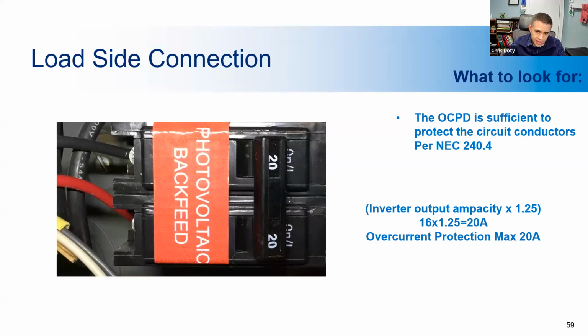Here you can see the standard calculation to determine the sizing of the circuit breakers and the fuses. Take 125% of the output current, and that's how you size it. This is to protect the wiring and the equipment in the system. As I said, most backfeed breakers will be double breakers, so they're 240 volt, which corresponds to what's in most homes. So you'll have equal distribution in each leg.